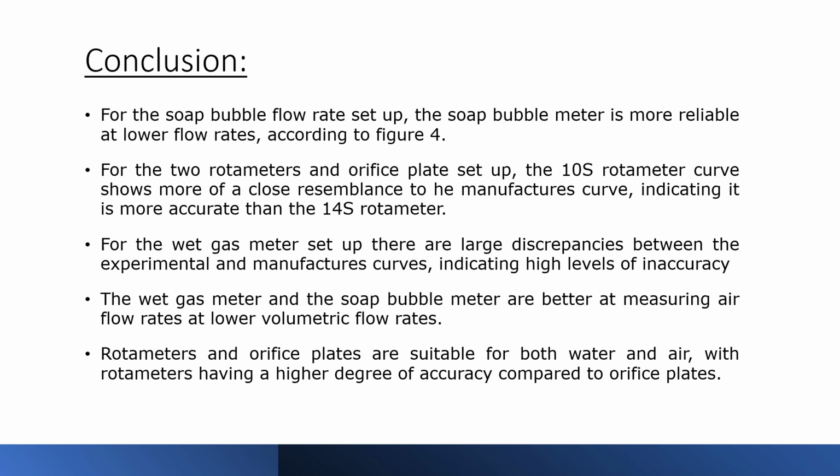For the two rotameters and orifice plate meter setup, the experimental curve for both the 10S and 14S show a resemblance to the manufacturer's curve. However, the 10S rotameter curve shows a closer resemblance, indicating it is more accurate than the 14S rotameter.